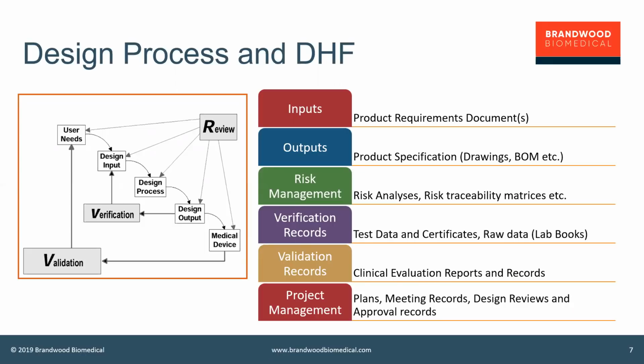So when you actually take the XFT, you talk about it and you decide that this document or this protocol, whatever it happens to be, is suitable for the design and development of the device. That's signed off by the XFT. That's your design review. And then finally, design transfer, those kinds of things as it's being pushed into manufacturing.